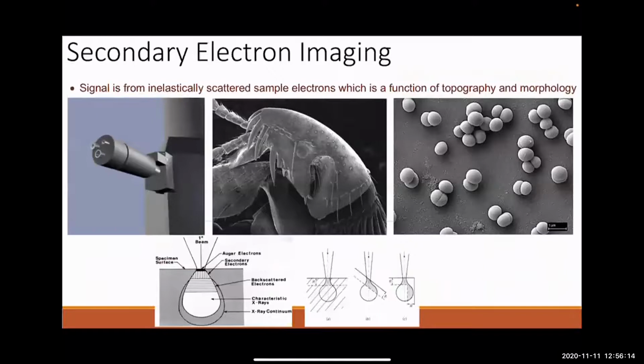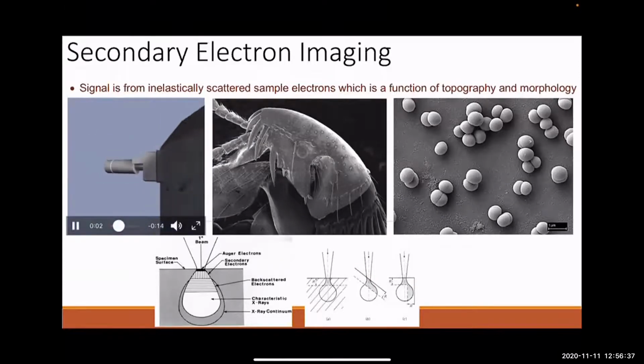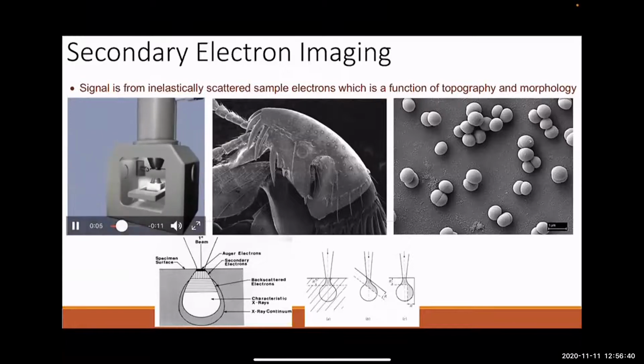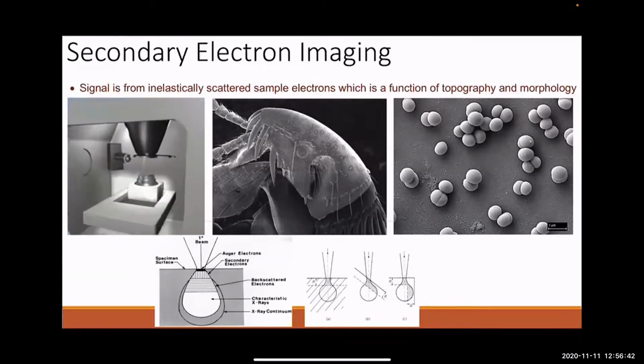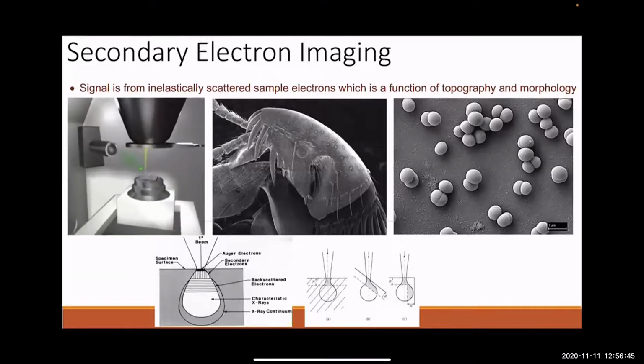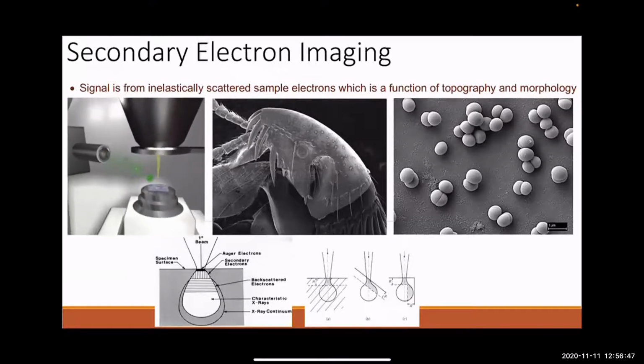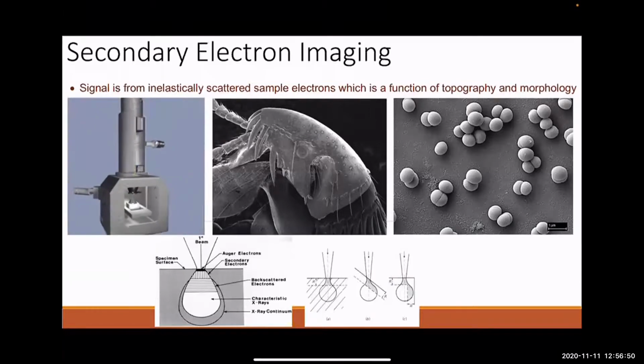Secondary electron imaging is probably what you see in the literature when you're perusing a paper and you see an SEM image. Probably greater than 90% of the time, what you're looking at is a secondary electron image, because the number of secondaries, remember, that's sample electrons that are being scattered out, is largely a function of the topography of your sample. So it's good for getting an image that is very much like what you'd see with a reflected light microscope, even though the image construction is very different. The image that you get can be interpreted in the same way.